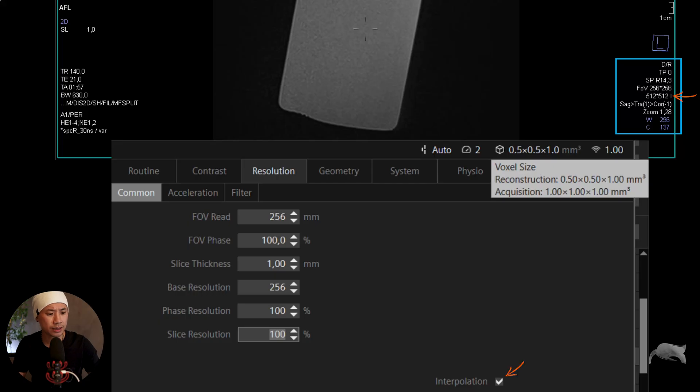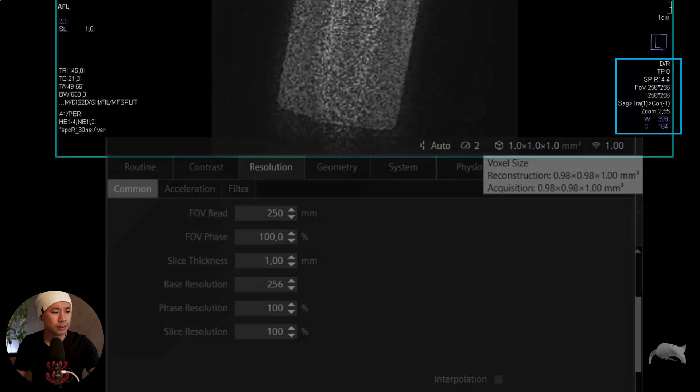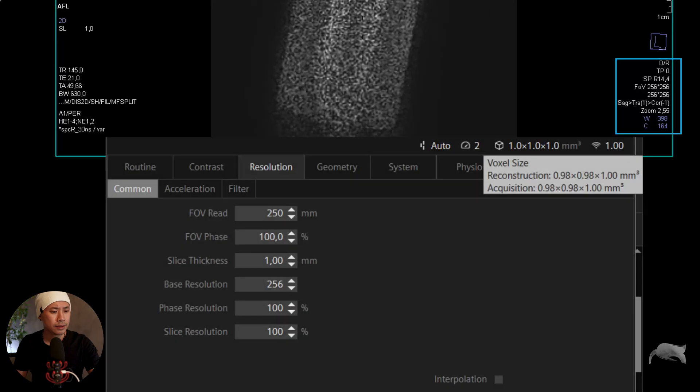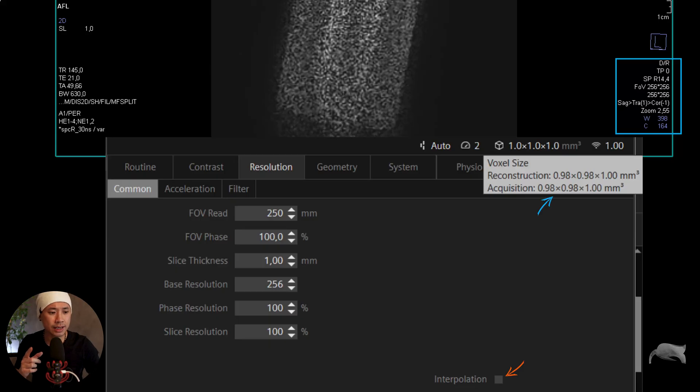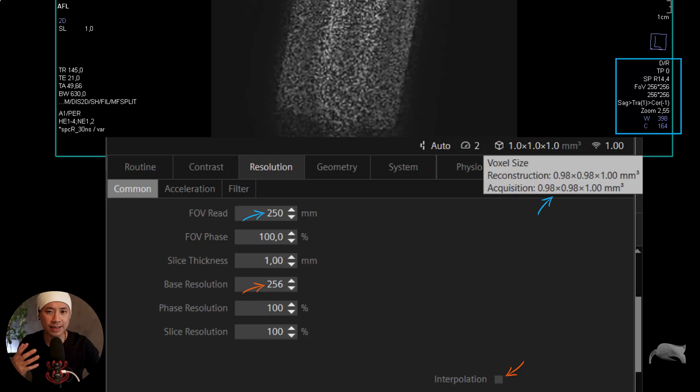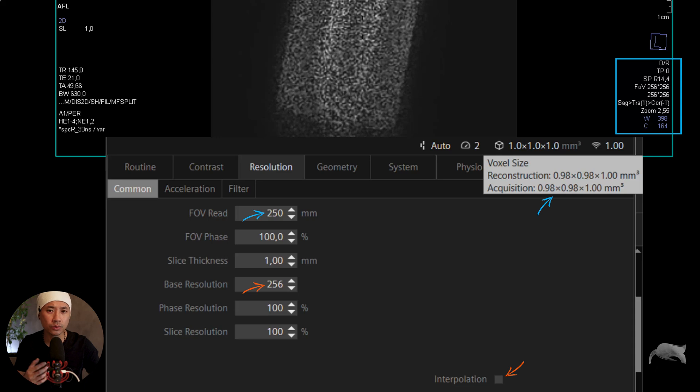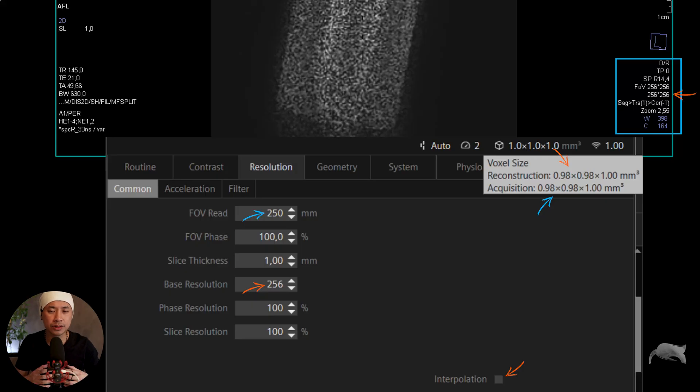It's also ticked on there - interpolated. So let's talk about something different. What happens when you turn off the interpolation, like here? As you can see here, it's now 0.98. Of course it is, because we're using a field of view of 250. If you take 250 divided by 256, you will get 0.98. So 0.98, 0.98, in one millimeter, and there's no interpolation function on. That's why the reconstruction is also the same - 0.98 on the upper row right here. So here is no 'i', no 'i' means there is no interpolation.